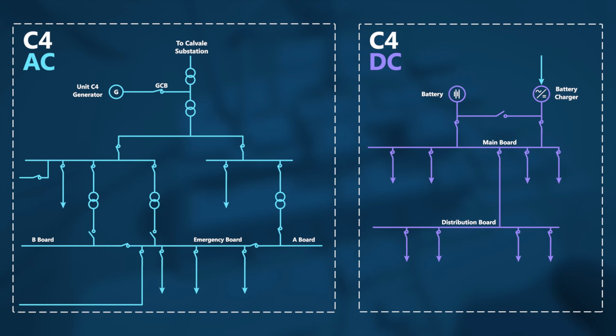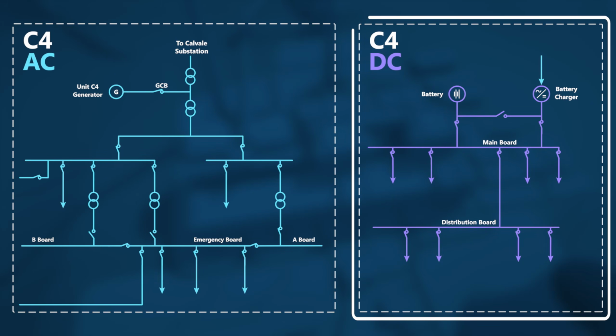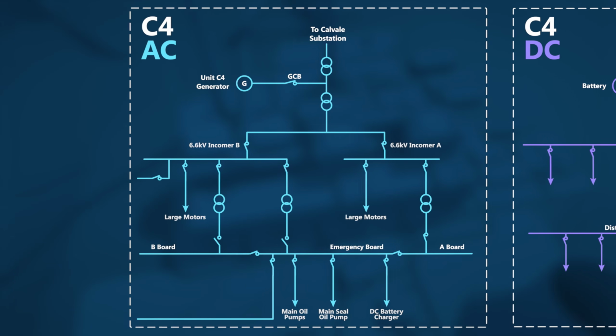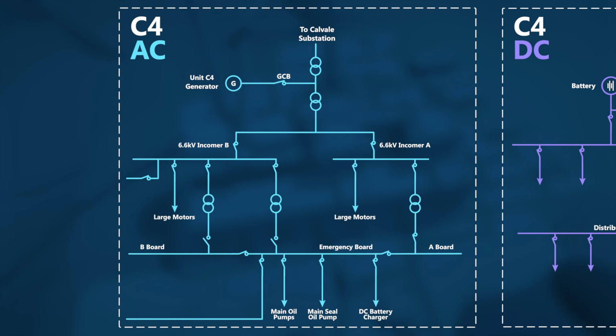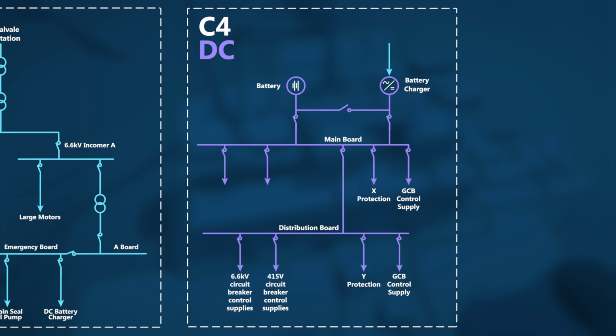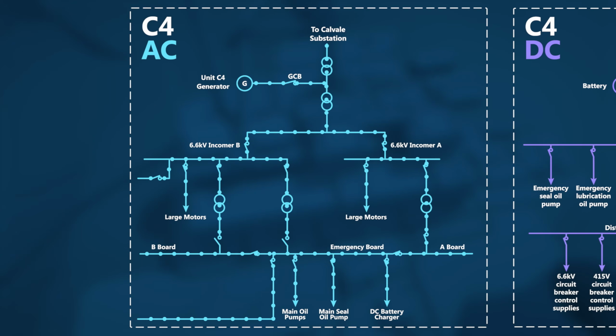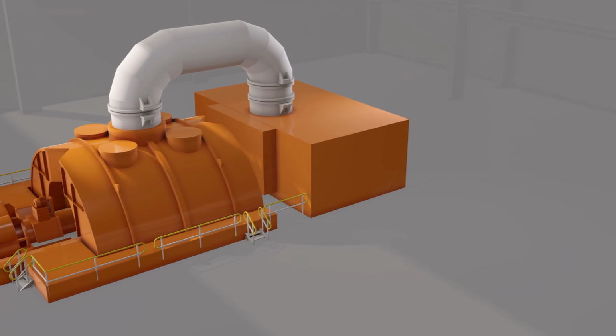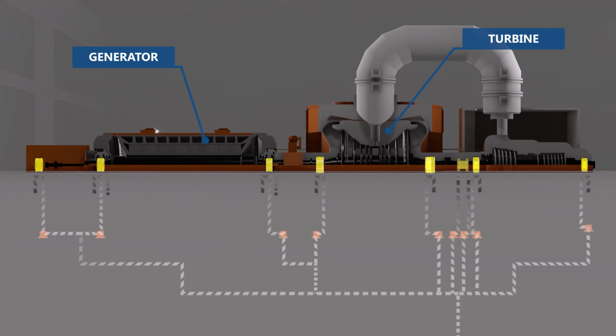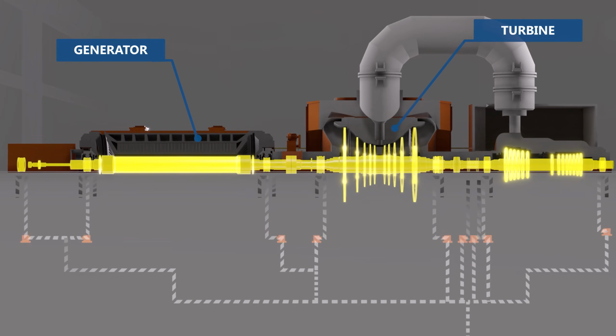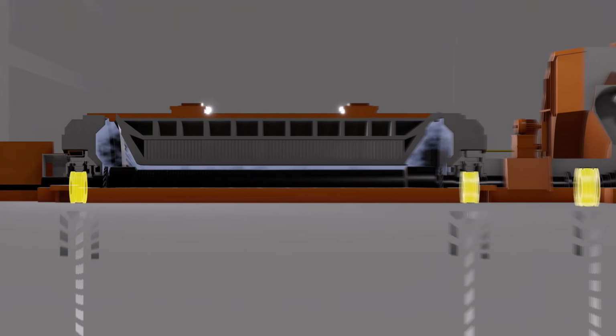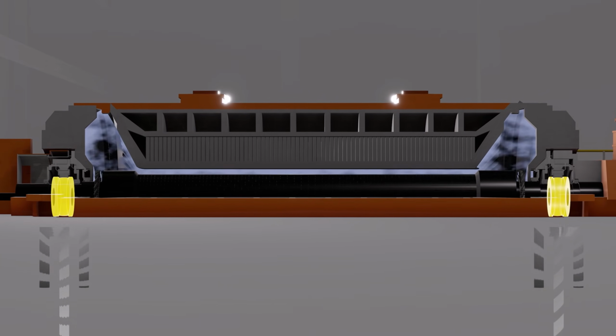The safe operation of Unit C4 relies on 2 key electrical systems, the AC system and the DC system. The AC system powers key equipment required for the operation of the turbine generator, whereas the DC system provides monitoring, control and protection, as well as backup functionality in the event of a loss of AC power. The AC system is connected to the grid and supplies large equipment. It powers the hydraulics that open and close the steam valves, which regulate the flow of steam to the turbines. It powers the pumps that provide lubrication oil to the bearings, allowing the rotor to spin freely without metal-on-metal contact. And it also powers the pumps that create an oil pressure seal, preventing the hydrogen gas that cools the generator from escaping.